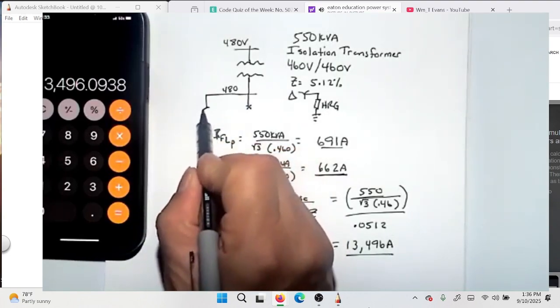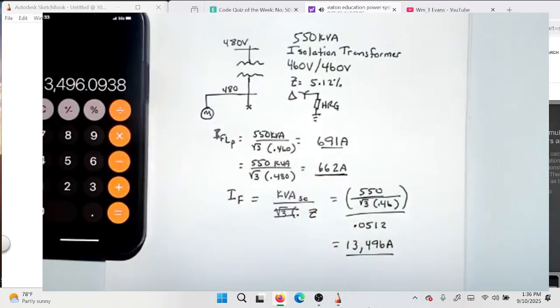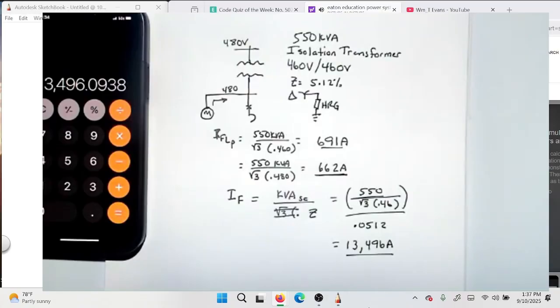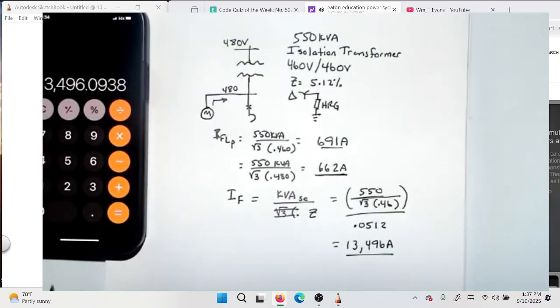Also, if we have motor contribution here, that motor contribution could increase the fault current for a short period of time during fault conditions. So again, these numbers are estimates. If that number was 13,500 amps and you were putting 35 kA breakers in on this system, it's not going to matter. It's so different that it doesn't matter. If this number was 34,000 amps and we weren't exactly sure what the impedance up here was going to do and the motor contribution was going to do, I would be much more concerned. So again, using these estimated calculations, we can go through that and figure it out.